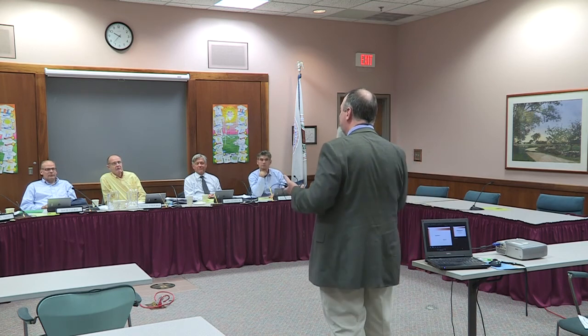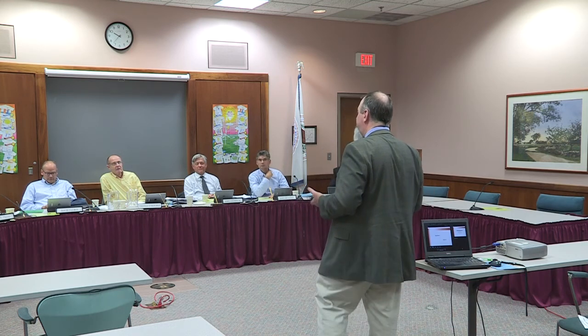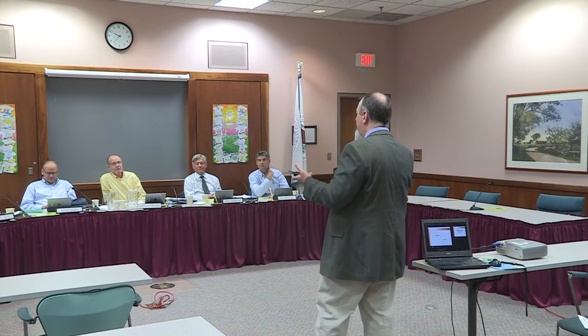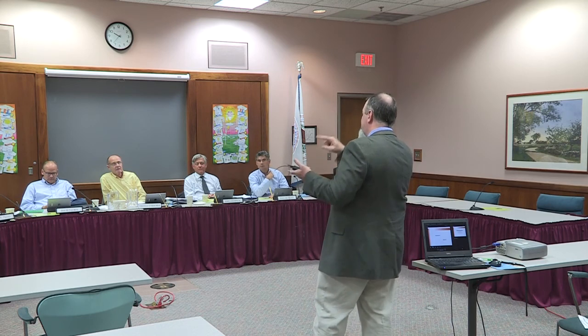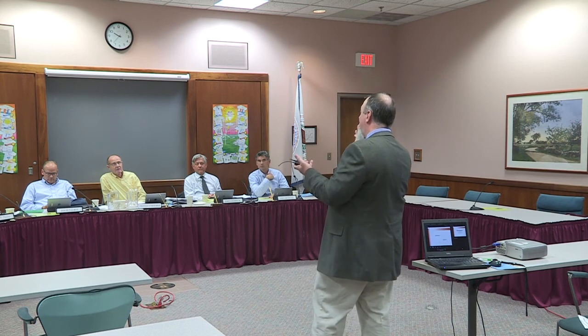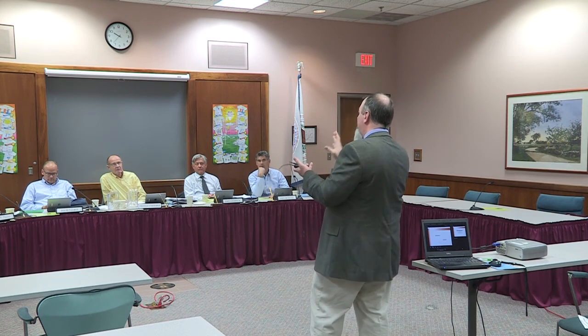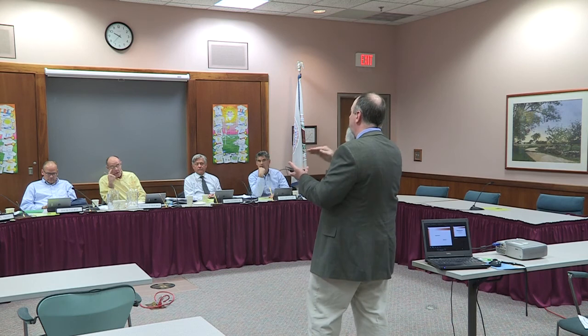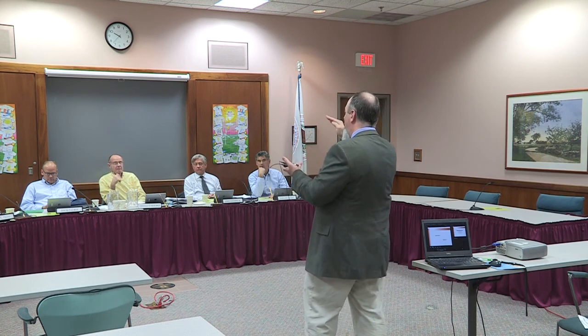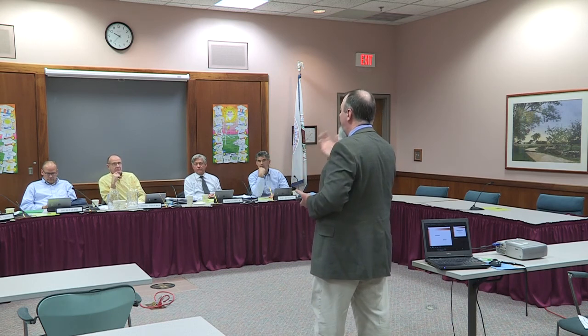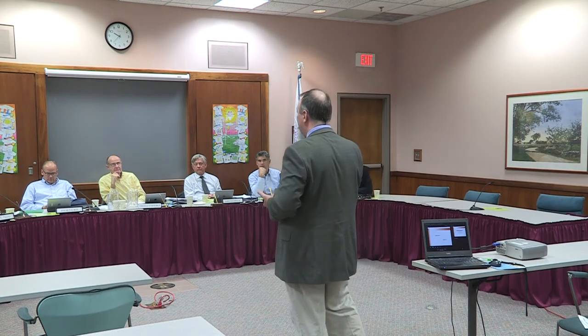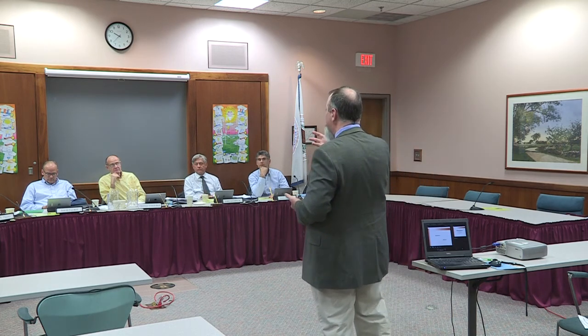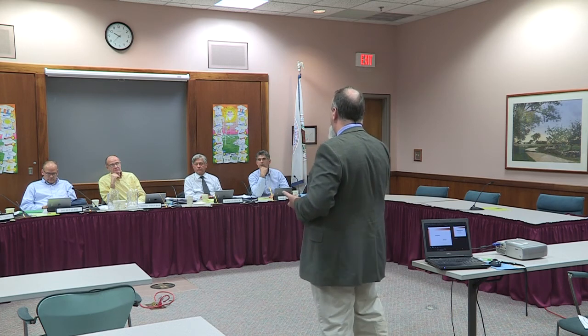It is a short circuit condition where current wants to continue on a path, and when you break that path it still wants to follow it. So when you open a switch on the system, it draws an arc, and with that arc comes heat, pressure, and combustion that can cause significant damage. The arc flash study calculates the potential of that energy at different points on the system.